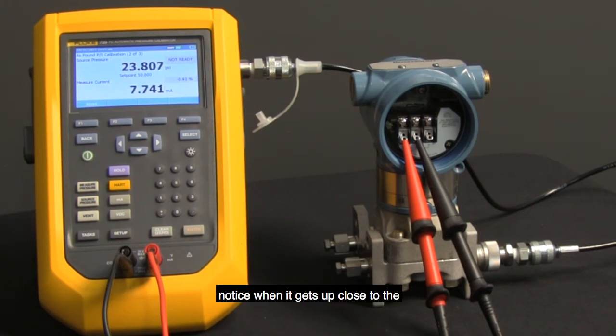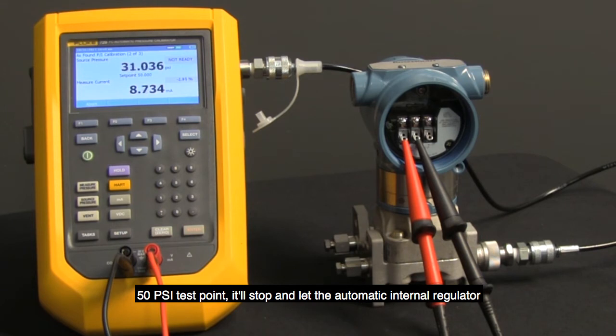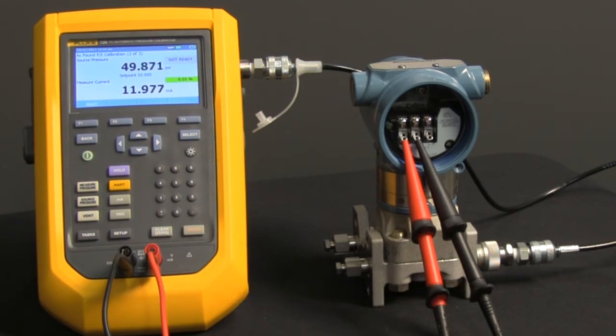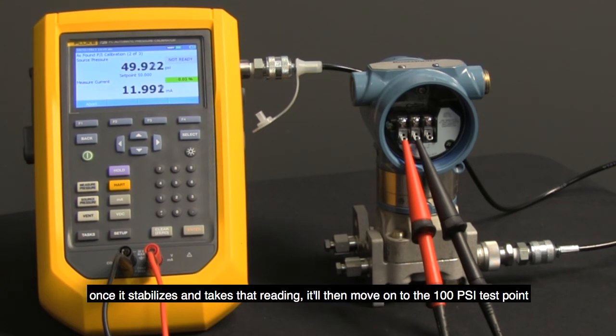Notice when it gets up close to the 50 PSI test point, it'll stop and let the automatic internal regulator fine-tune automatically and hold steady at that 50 PSI test point. Once it stabilizes and takes that reading, it'll then move on to the 100 PSI test point.